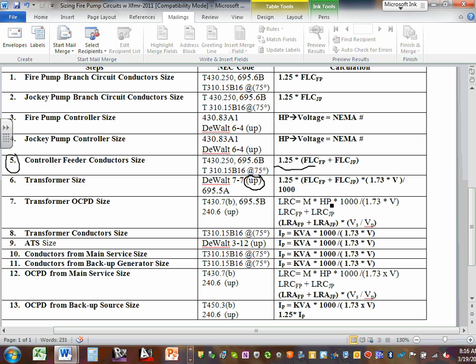Look what happened. This is slightly different. You take the locked rotor current of the two of them, exactly like we did. Then you have to multiply it by the voltage ratio. This is the unique part. After you do what we have just done, you multiply by the voltage ratio, because you're calculating at 208, guys, and you're transferring it to 480. So you have to take the voltage ratio into consideration. That's new. Did you guys hear me? You multiply by the voltage ratio.